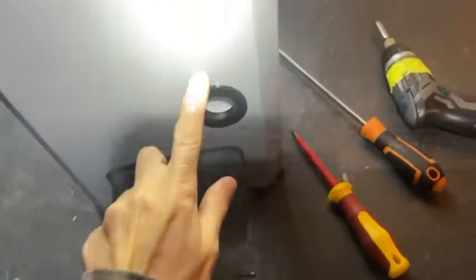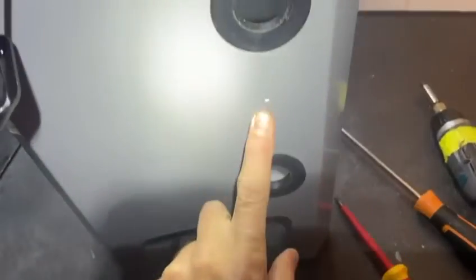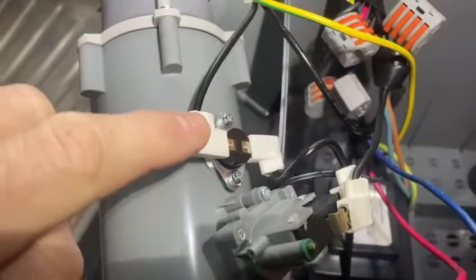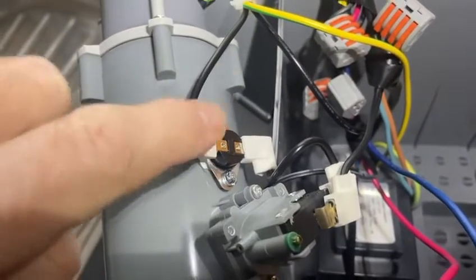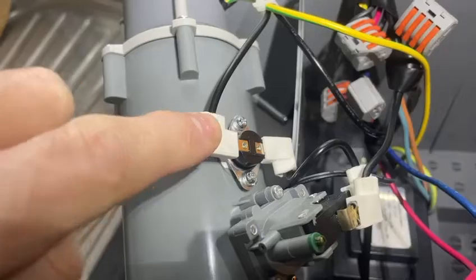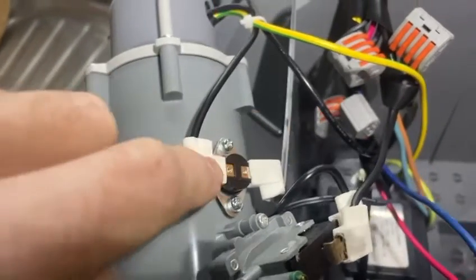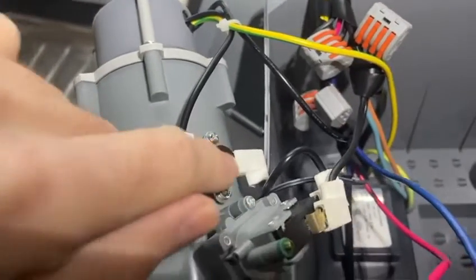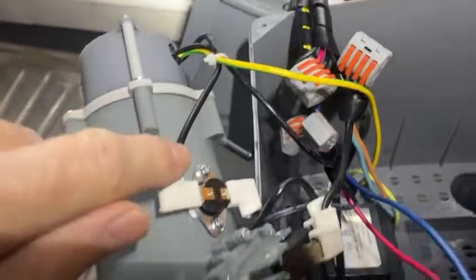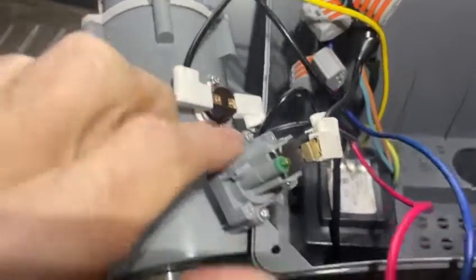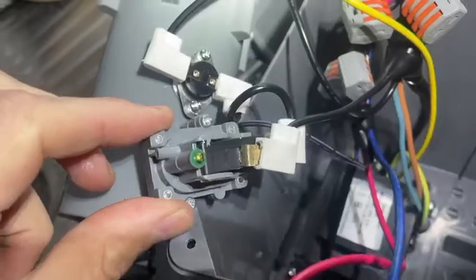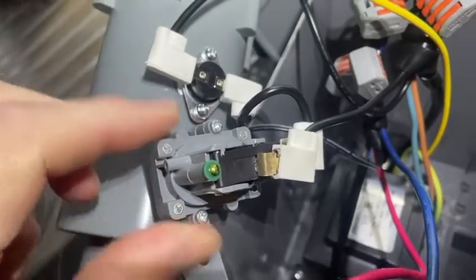So there's the reservoir out, we just undo that screw here and it pops out. On your reservoir, the heating element's inside here, and there's a thermal cut switch. When that reaches a certain temperature, around 50 degrees, that should cut the power also as a safety measure. These don't always work. I mean, your water pressure sensor's there.